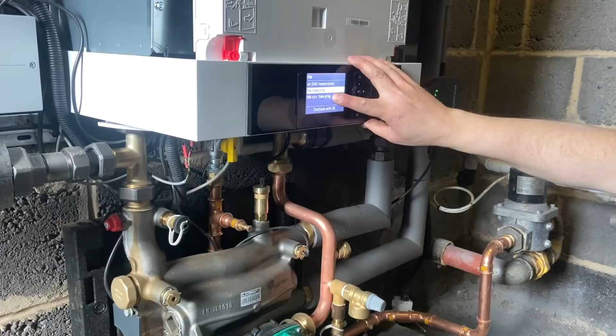Nice. So just explain the low loss header. Okay, so we've got primary side coming in from the boiler into the low loss header. It's going out on that one, coming back on here, and there's separation. I've never seen a cutout of this, so I'm quite interested myself on these. I've done a few of them. It's normally just a big chamber though, isn't it? Yeah, it's kind of an open chamber. That's the boiler pump. So there's no pump in the boiler. No pump in the boiler. That's the pump externally, and that's pumping.